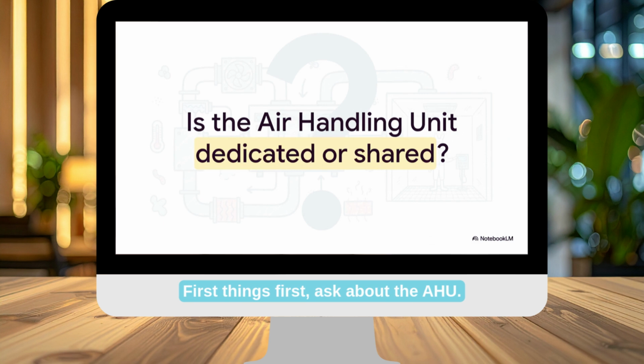First things first, ask about the AHU. Is it dedicated to a single sterile zone, or is it shared between different areas? In critical environments like pharma or hospitals, a shared AHU is a huge red flag. Why? Because it creates a direct pathway for cross-contamination between rooms. You always want dedicated units for your most sensitive zones.